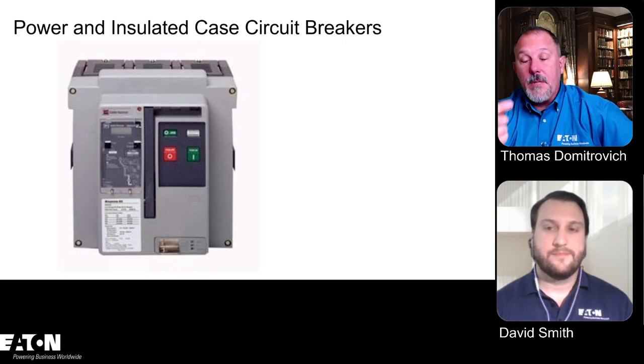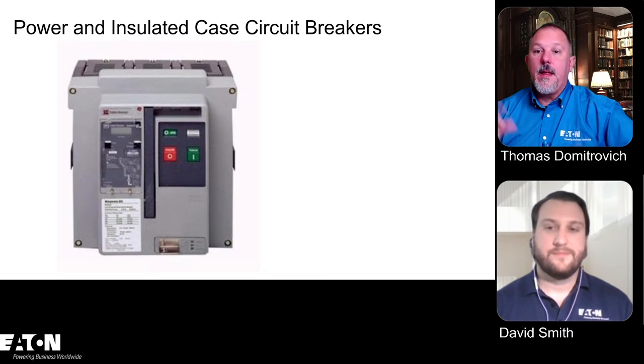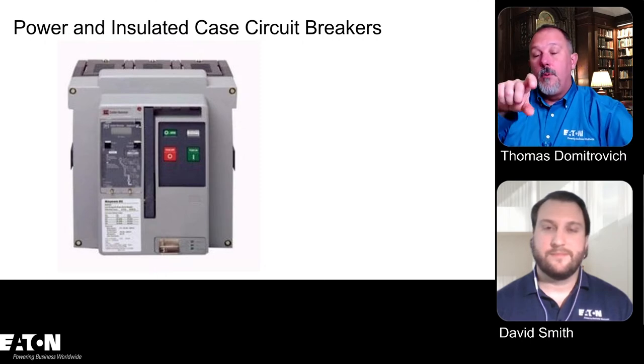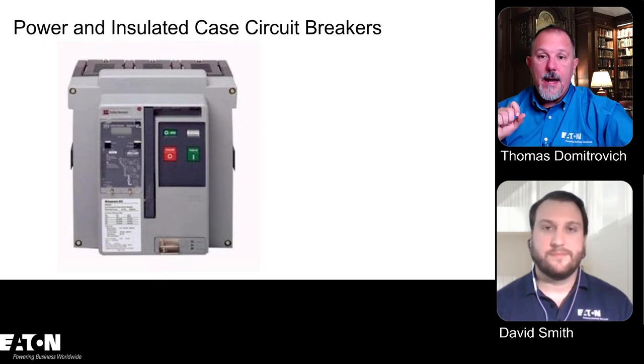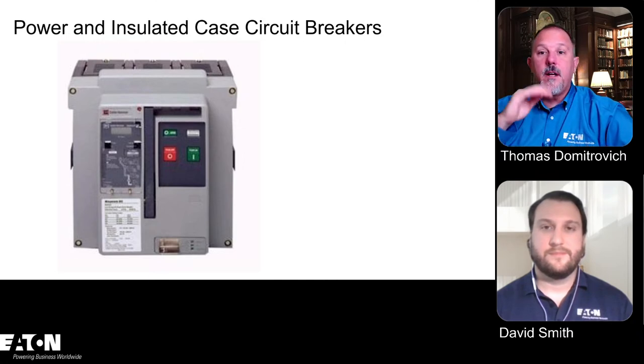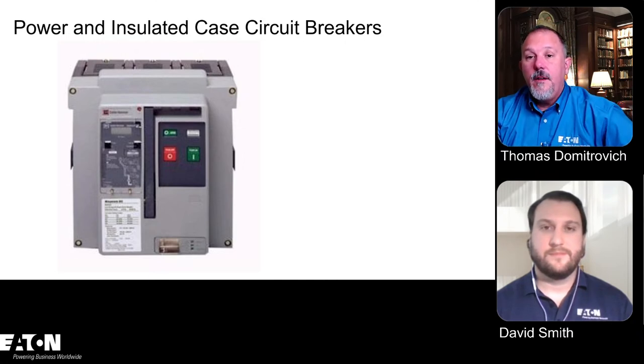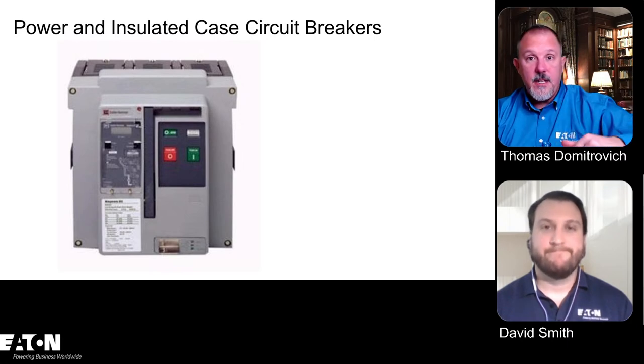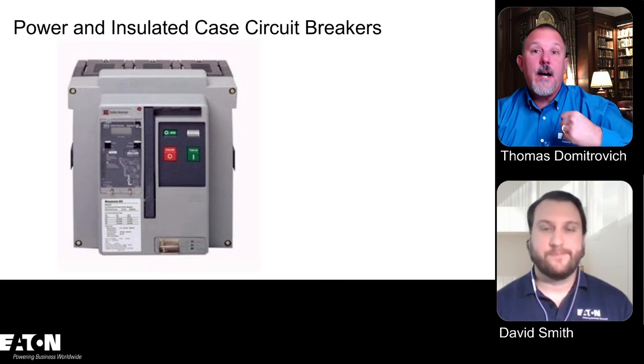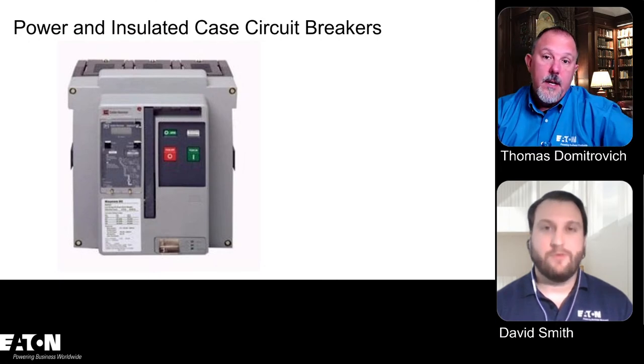What that's speaking to is when I take that 3,000 amp frame or 2,000 amp frame and put a 1,000 amp plug in there, that means that breaker, without shutting it down, pulling it out, unscrewing it, and putting in a higher rated plug to take it to a higher number, is very similar to saying, okay, I'm going to take a fuse out of my 1200 amp switch. There's an 800 amp fuse. I'm going to shut it down, take that 800 amp fuse out, and put a 1200 amp fuse in. Right. So it's very similar to that.